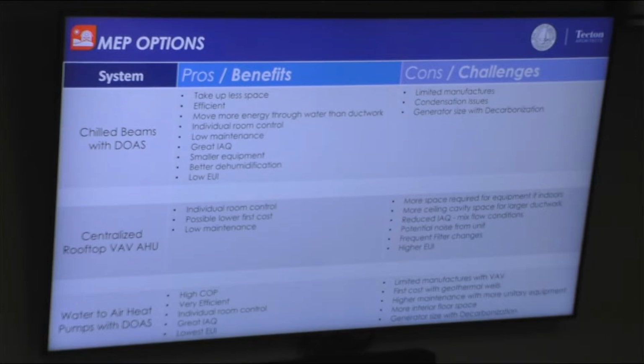Cons, there are only 2 manufacturers that do VAV heat pumps on the market right now, and that's what we want to use for efficiency, but there are only 2 manufacturers. First cost, again, the geothermal wells, the decarbonization one, that's what you need if you go water to air. Higher maintenance, more unitary equipment. A school like this, you'd probably need 28, 30 of these heat pumps around. That's 30 little compressors you've got to maintain and deal with on a yearly basis.